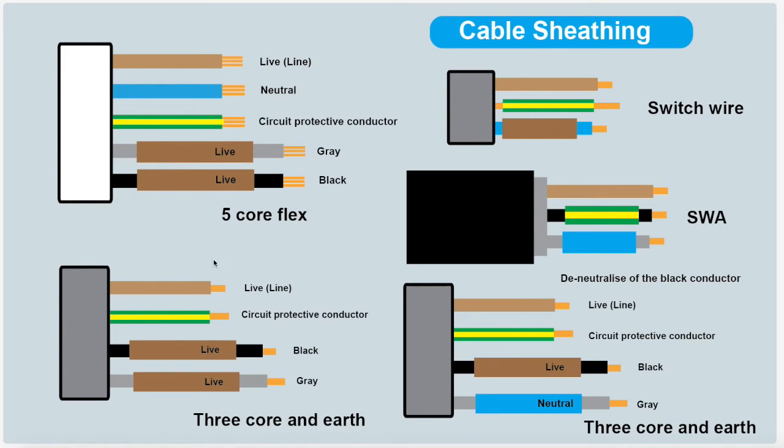Same on your 3 core and earth. Your brown would be your live. Your green and yellow sleeving would go over the bare copper conductor. That's only ever used as your circuit protective conductor. We sleeve that in green and yellow. And again your brown, your black and your grey would be sleeved in brown sleeving if they are switch wires. Now of course you've got the example in the 3 core and earth where you do need a neutral. So you've got your live, your brown, your CPC, the bare copper, that's your CPC. Now you've got your black and your grey. Now the guidance is that for the live conductor, for the black, you would sleeve that in brown sleeving. And you would use the grey as the neutral conductor and you would sleeve that in blue sleeving.